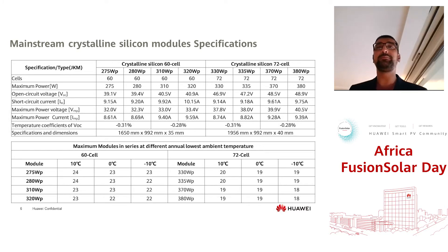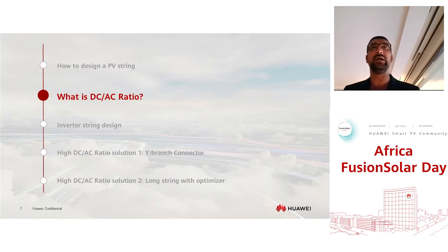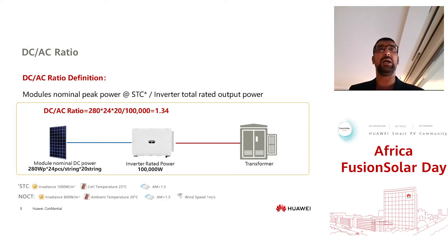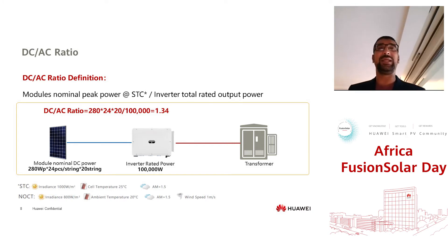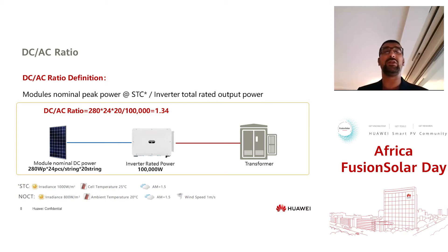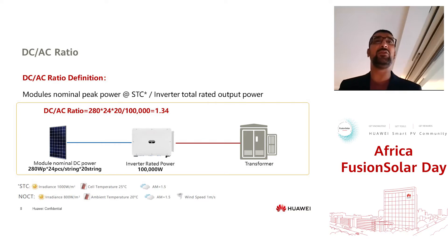If temperatures get as low as minus 10°C, that would be limited to 22 PV modules per string. The DC to AC ratio is defined as the nominal peak power at STC divided by the inverter's total rated output power. With the 280W PV modules, 24 modules per string and 20 strings into one inverter divided by the 100 kW nominal inverter output, that achieves around 1.34 — what we call a 34% oversizing ratio on the inverter. This is based on STC conditions, typically around 25°C.